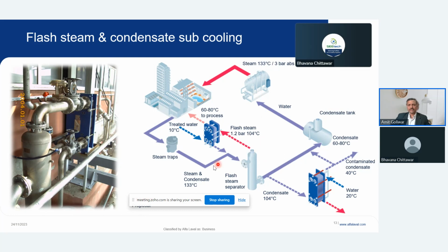However, the problem is this complete system is under pressure. And many a time, if there is a back pressure, it has been observed that the condensate will not come out from the equipment easily because there is very little differential pressure. What we propose is to put this condensate in a flash vessel, take the flash steam out of the flash vessel, use a heat exchanger, utilize this heat to preheat your process water and bring condensate to atmospheric temperature, atmospheric pressure. If you feel, you can even subcool this by using another heat exchanger so that you get condensate at 60 to 80 degrees. And with 60 to 80 degrees, it is very easy to manage condensate, and then you can pump it back to the boiler, wherein you can use this water as a recovery of water.